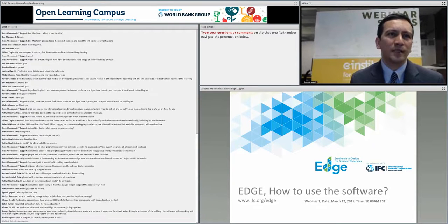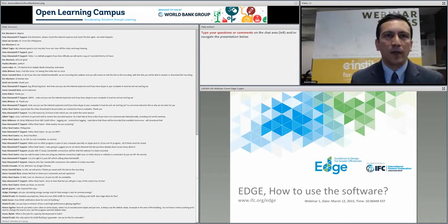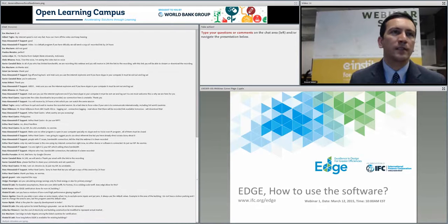There's a question from Satish Kumar asking how EDGE certification will be done for non-AC buildings, not air-conditioned buildings. That's a very good question. EDGE will certify all buildings, either conditioned or non-conditioned. If your building is completely naturally ventilated and passive, EDGE can still certify it. If you select no heating and no cooling, basically the cooling and heating energy moves into virtual energy, but passive measures to reduce that will still be recognized in the EDGE savings. So the thermal comfort measures are counted as virtual energy on EDGE. Again, you can read more about that in the methodology report, and I'm happy to answer in more detail if you wish.